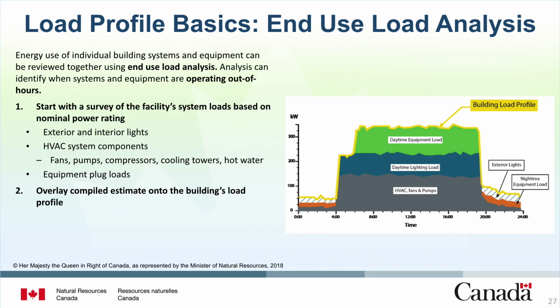In this chart, load profiles for daytime equipment and daytime lighting and HVAC fans and pumps are aggregated to equal the building's load profile. Profiles for exterior lights and nighttime equipment are also included. This comparison identifies what equipment is operating during occupied and unoccupied hours and estimates associated energy use relative to the building load. Additional investigation can be undertaken based on the difference between expected and actual load profiles. For instance, a night walk through the building can identify equipment that is operating unnecessarily after hours.